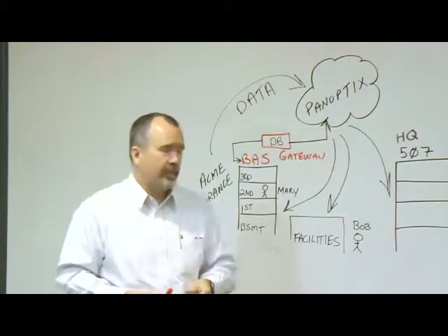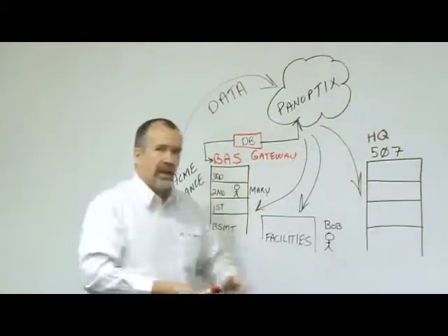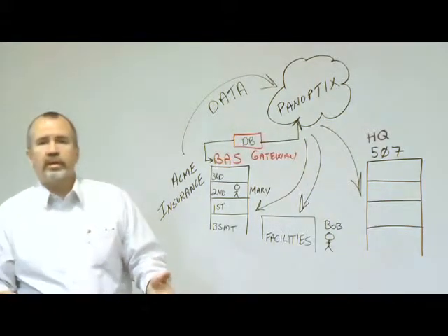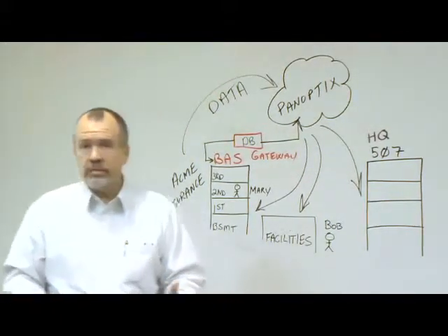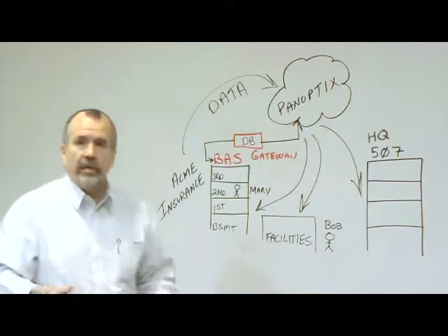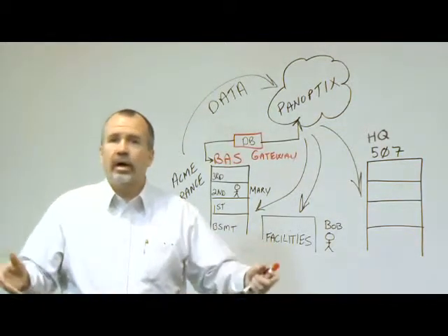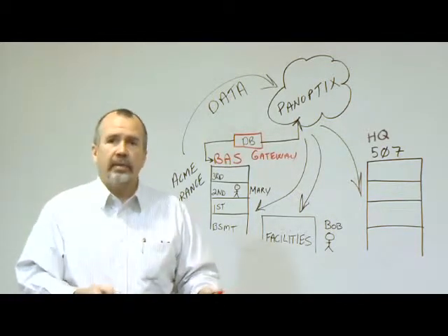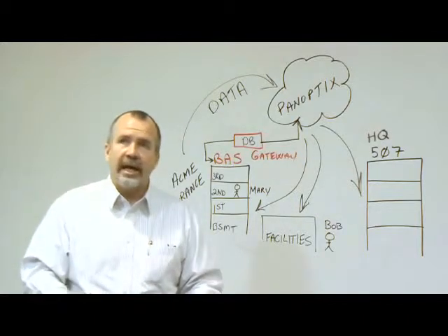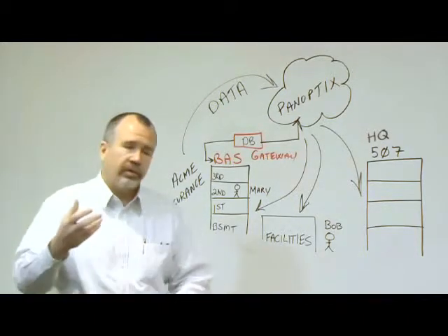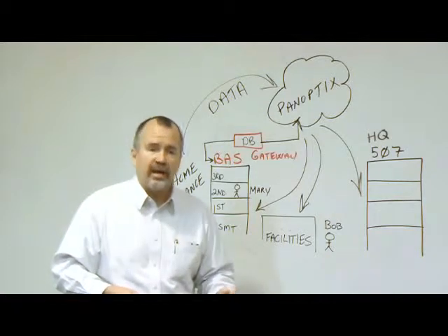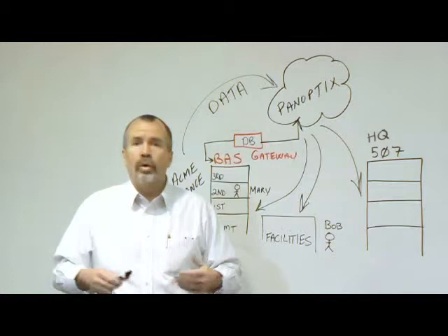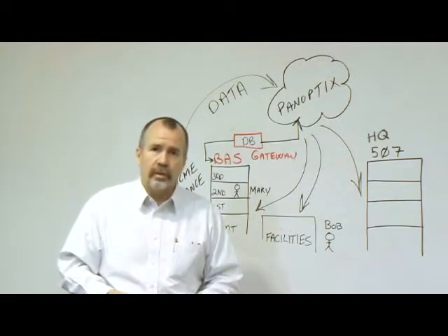The typical response would be to have Bob take off from facilities, jump in the elevator, travel up to the second floor, and interview Mary to determine what the symptoms of the situation are. Well, it's hot. Bob's immediate response is to begin dividing and conquering to try to determine the source of the issue. He'll drag his ladder back up, he'll set it up, he's interrupting Mary's day, he's popped the ceiling tile, he crawls up above the ceiling tile, inspects the VAV box, potentially to determine that there really isn't a problem with the box, or the thermostat, or the cabling in the room.